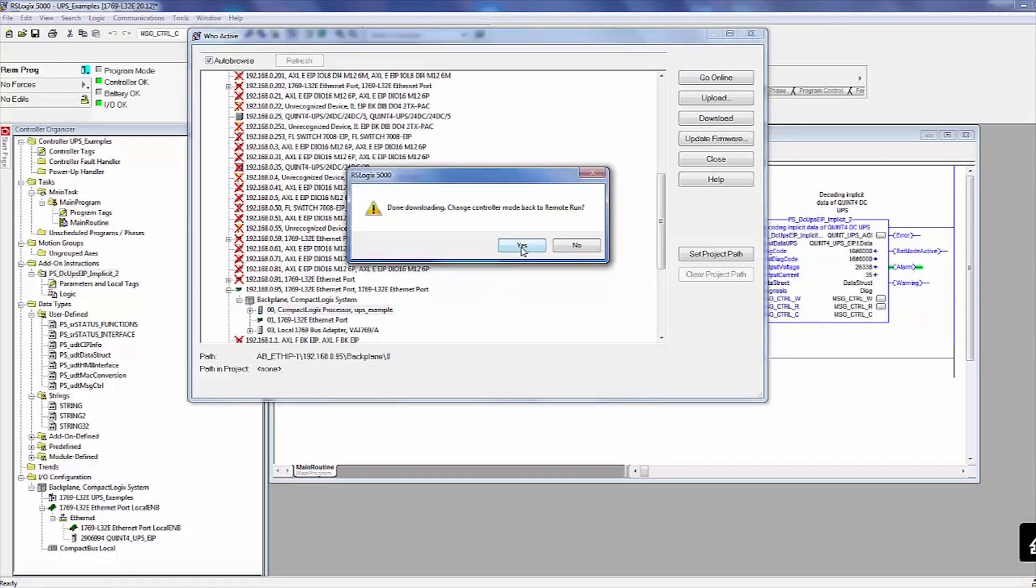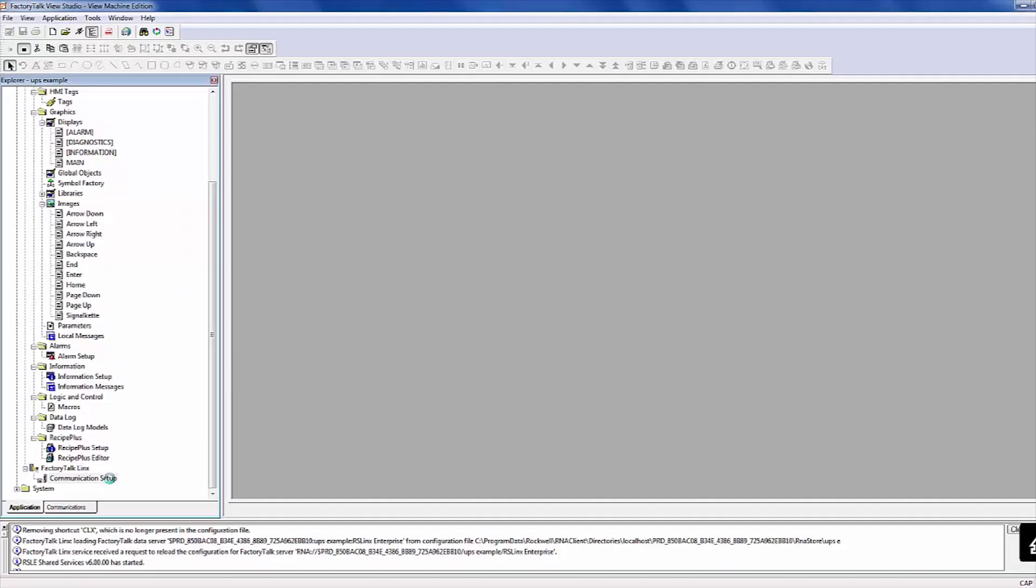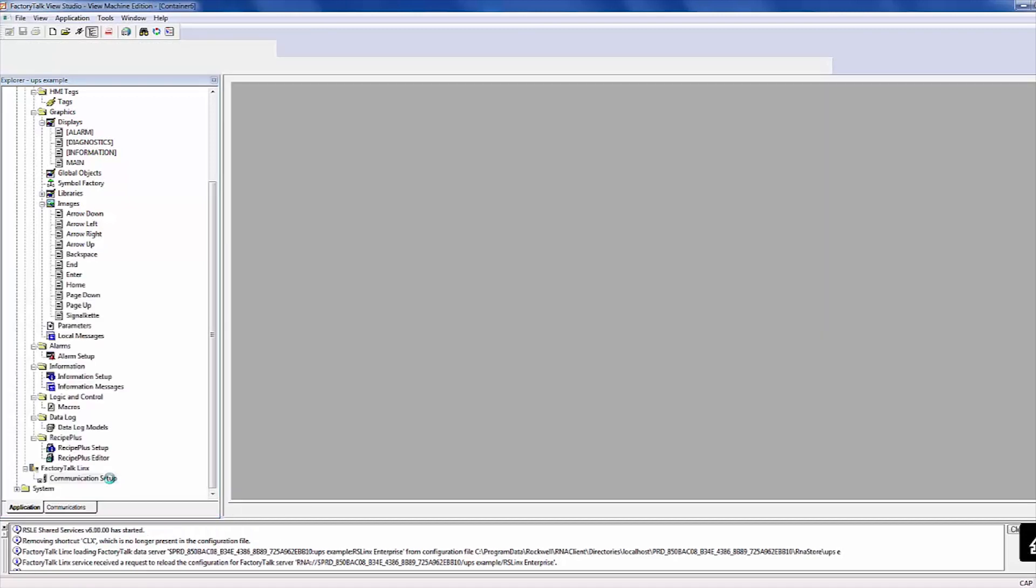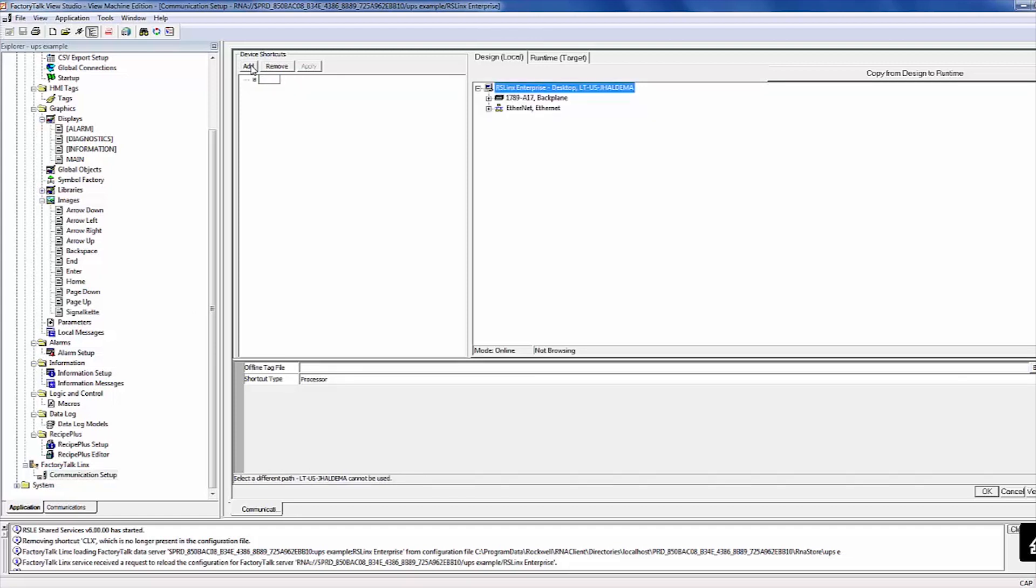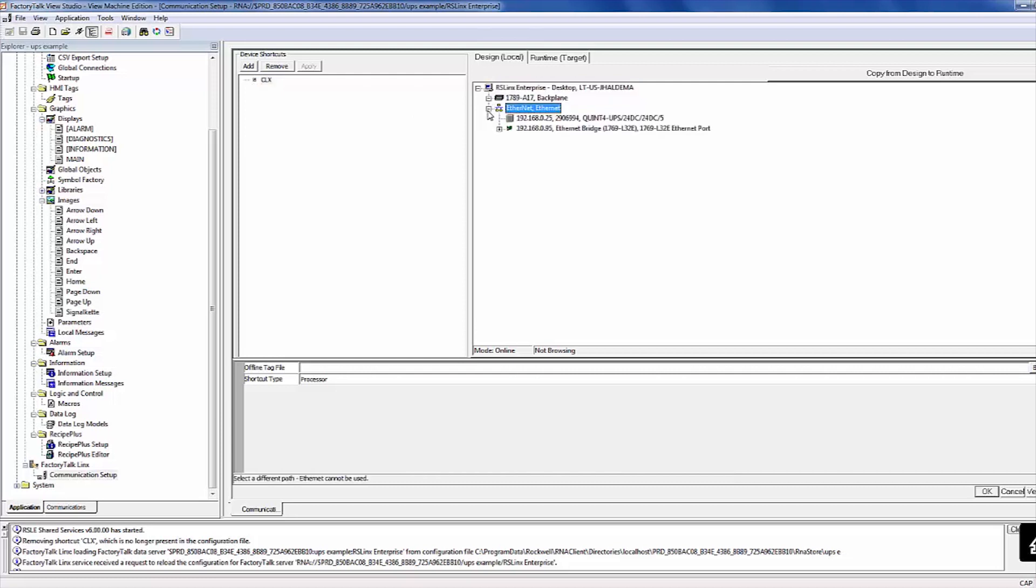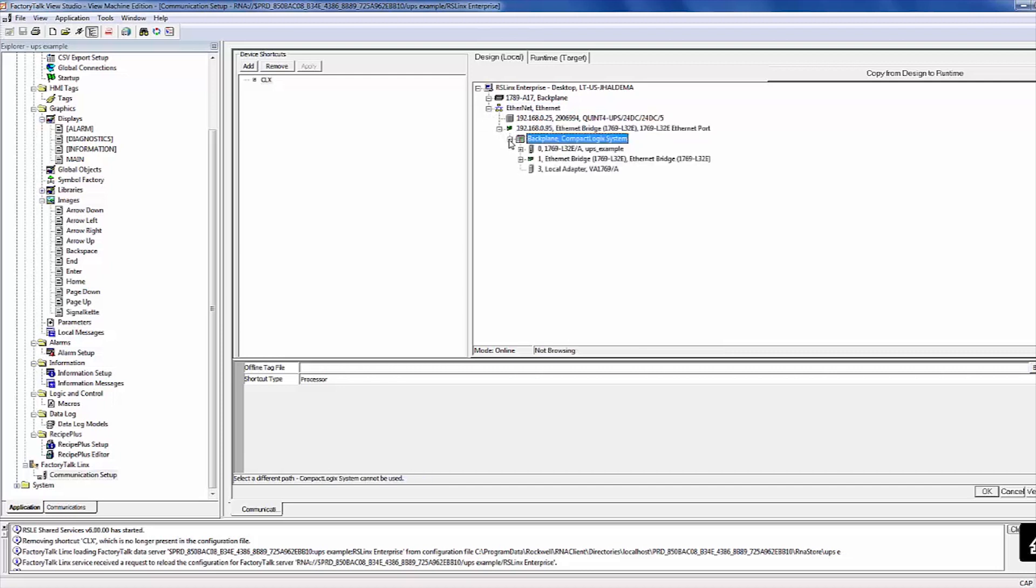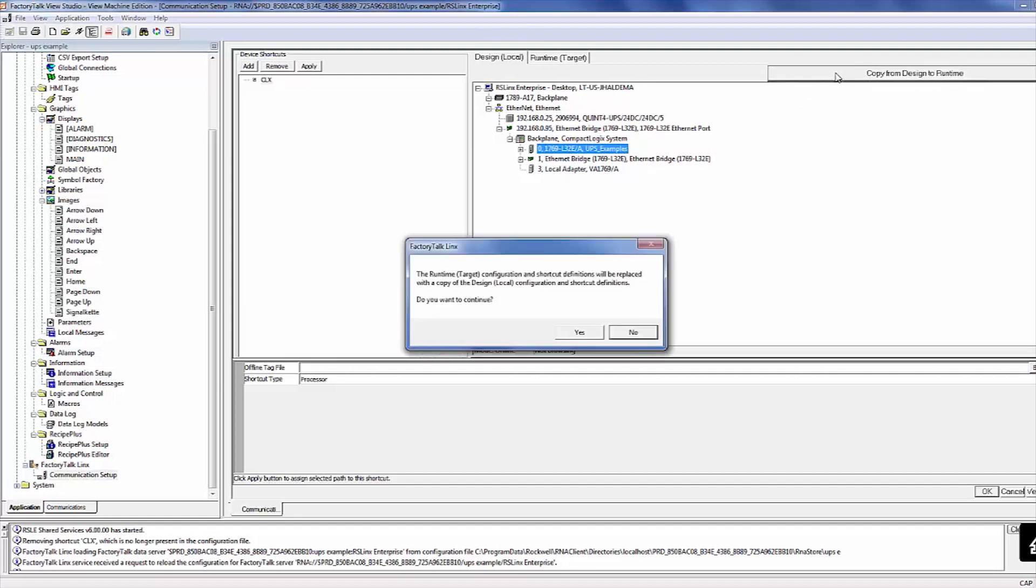The PLC project is now complete, so move over to Factory Talk View to set up the HMI screens. Once the project is open, right-click the Communications Setup and select Create New Configuration. Click the Add button, enter a name for your connection, and browse for the PLC we just programmed. Once you have highlighted the PLC, hit the Copy from Design to Runtime button, then confirm and apply your changes.